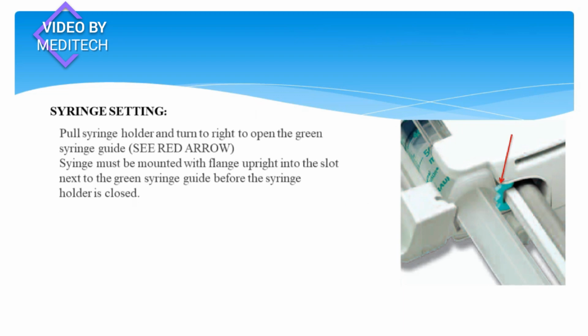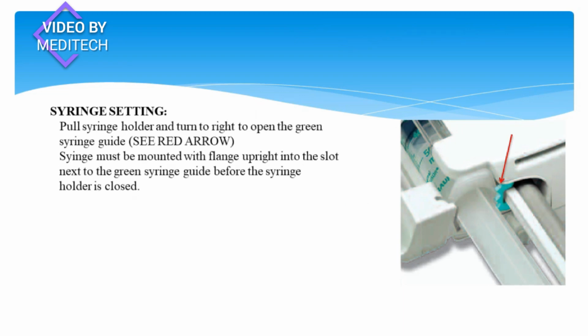Syringe settings. Pull the syringe holder and turn to the right to open the green syringe guide. See red arrow. The syringe must be mounted with the flange upright into the slot next to the green syringe guide before the syringe holder is closed. Make sure that the syringe is properly held in place.